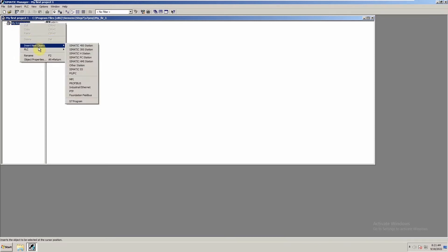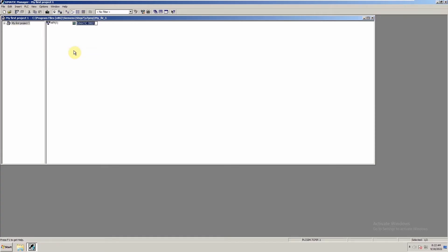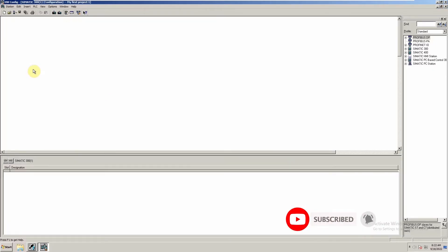We will right-click and go to Insert New Object, then click on the SIMATIC S7-300 station. There are a few other options here like 400 station, PC HMI, and PG/PC, but today we will select the SIMATIC S7-300 station. Once our station is added, we can open it and see the hardware configuration option. We will double click on it to open the hardware configuration window, which is used to configure the hardware for this project.